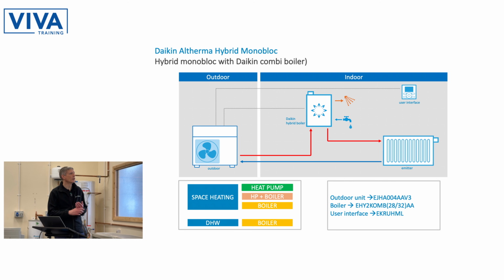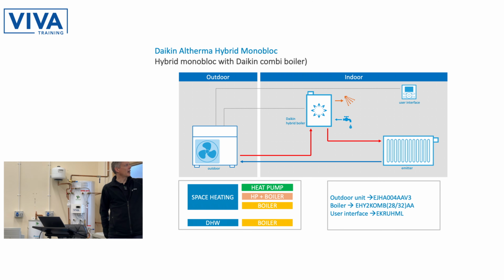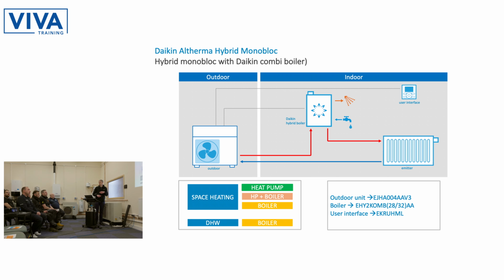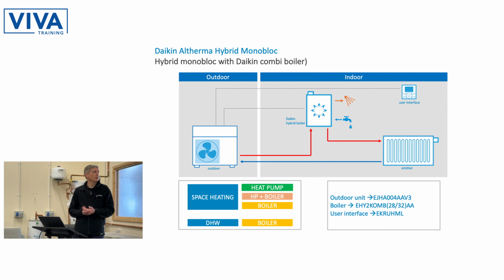So this is the schematic I showed you before. On space heating, they're in series, so you can have the heat pump only operating. The boiler then pumps through the boiler, but the boiler doesn't add any heat. If the heat pump can't deal with that, and I'll come to that in a minute, the boiler will start adding some heat into the heating system as well. Or just the boiler can operate, and again the heat pump's still in the circuit, but the water will just pump through it, and the boiler will be adding all the heat. So for space heating, we've got those three modes of operation.